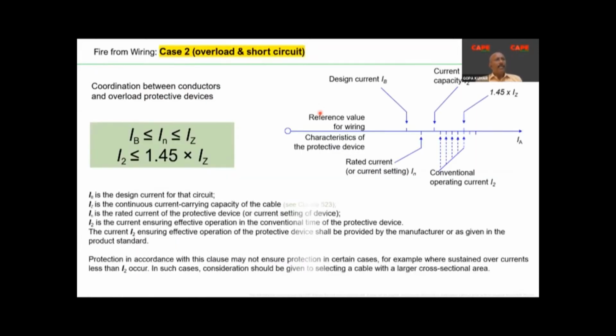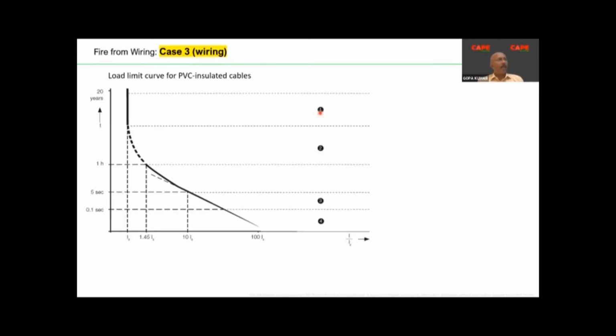Then the second part, the selection of the protective device and the wires, is very critical. The coordination of the protective device and the wires shall be made in such a way that the protective device is able to protect your installation from overload and short circuit. Installation means the wiring. The MCB, for example, is supposed to protect your wiring, not the equipment. But the same MCB shall protect in case of any shock hazard in your building. So for fire, the protective device and the disconnection times are very much coordinated. These are very well documented in the standard.